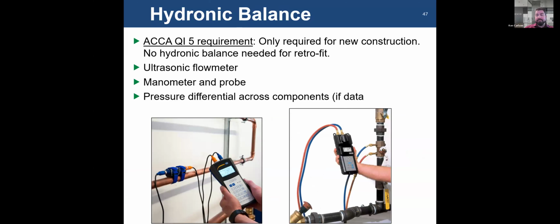Water balancing, probably any installation with a common boiler, nobody's doing water balancing, right? You turn your pumps on, maybe you've got some temperature control or something like that, but that's about it. Nobody's actually verifying any water flows. On these newer systems, heat pump systems with electric boiler backup and different zones and different pumps, mixing valves, buffer tanks, everything like that, you'll need to measure flow to make sure that you're not blending water in the wrong direction. So, not necessarily a big common practice these days. Commercially, it's done all the time. Residentially, not so much, but this will likely be needed as the systems get more complicated.